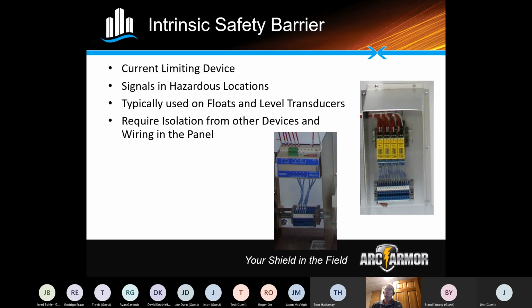So in a control panel, this is what the barriers are going to look like. In these two pictures, you can see that the barriers are installed in a different location in the panel, and they actually have a shield around them. That was standard practice up until a couple of years ago, when NEC and UL relaxed that. Shields are no longer required, but there now is a 2-inch air gap required around any of the intrinsic safety areas. Most of the time you're going to see light blue wiring coming in where it's still on the hazard side of the barrier, and then on the downstream side of the barrier, it will revert back to normal panel wiring.